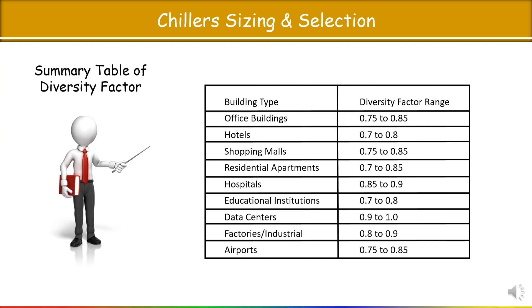Here is a summary table for diversity factor by building type. For an office building, the diversity factor range is 0.75 to 0.85. For a hotel building, a different range applies. The diversity factor ranges between 0.7 to 0.9 overall. The exact value depends on your building type — residential apartment, hospital, etc. Understanding the diversity factor is very important.